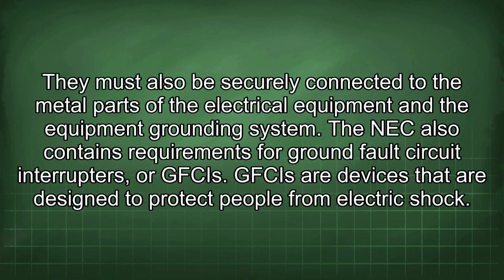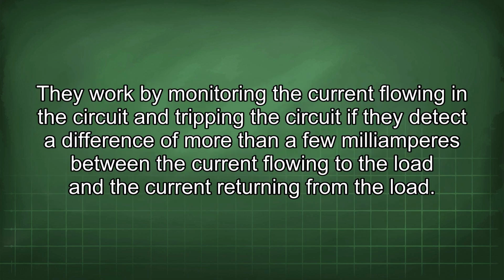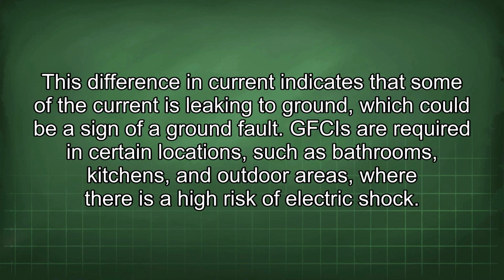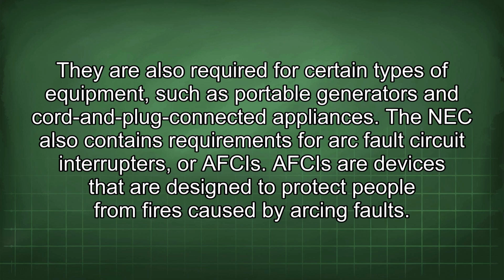The NEC also contains requirements for ground fault circuit interrupters, or GFCIs. GFCIs are devices that are designed to protect people from electric shock. They work by monitoring the current flowing in the circuit and tripping the circuit if they detect a difference of more than a few milliamperes between the current flowing to the load and the current returning from the load. This difference in current indicates that some of the current is leaking to ground, which could be a sign of a ground fault. GFCIs are required in certain locations, such as bathrooms, kitchens, and outdoor areas, where there is a high risk of electric shock. They are also required for certain types of equipment, such as portable generators and cord and plug-connected appliances.